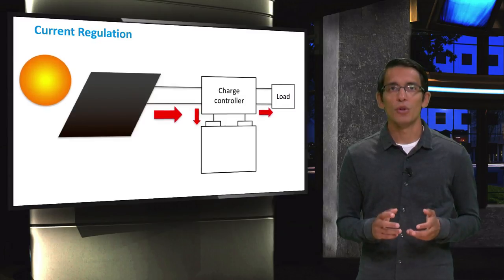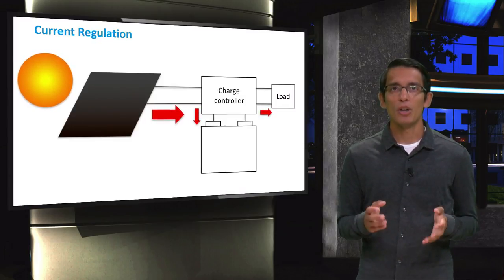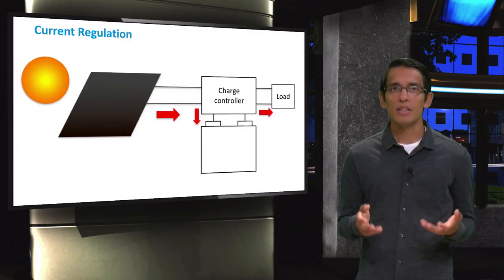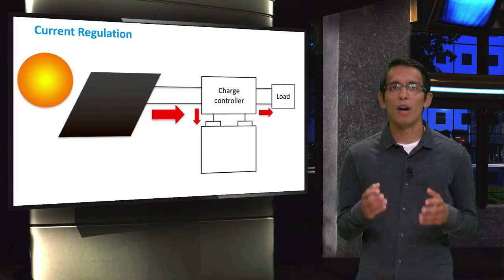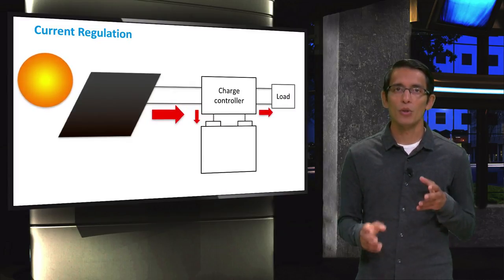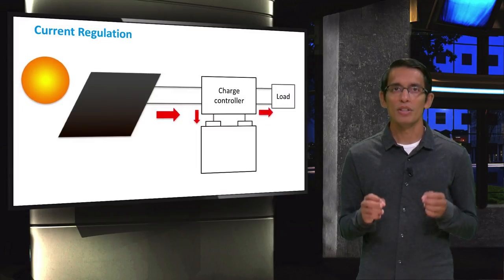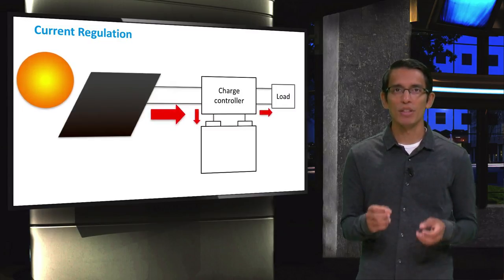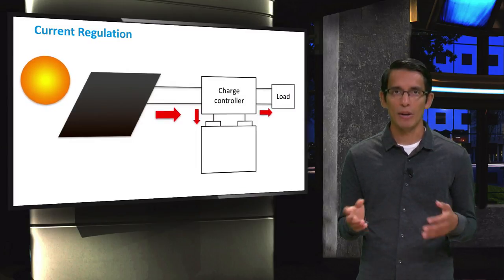Another function of the charge controller is current regulation. Consider a battery which is being charged or discharged at a faster rate than a nominal rate. This leads to a reduction in the efficiency of the battery. But a charge controller with a proper current regulation can be used to control this by maintaining the rates close to its C-rate, which is the battery's nominal parameter. The charge controller does this by imposing limits on maximal currents flowing into or out of the battery.